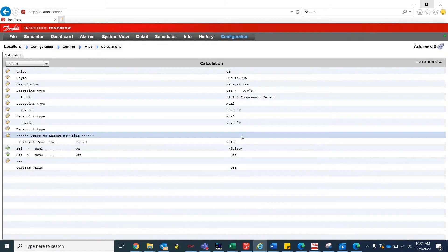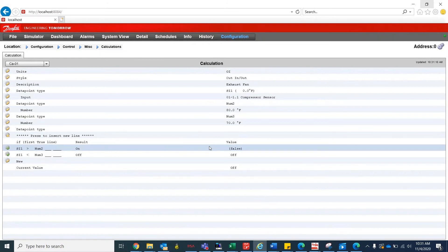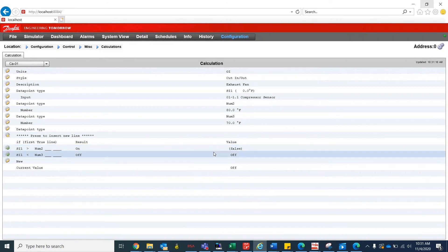So when we look at the bottom half of this calculation, we can see that when SI1 reading is greater than num2, the result will be on. And when SI1 reading is less than num3, our cut-out limit, the result will be off.